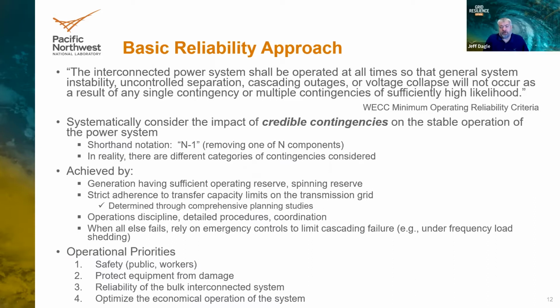There are important measures like spinning reserve, having more generation online than needed at any given time, and emergency controls. If frequency is high, that means we have more generation than load; if frequency is low, we don't have enough generation. If we need to trip generators to protect them from damage, that would be bad if we already have a low frequency condition. So utilities install under frequency load shedding as an emergency control to bring things back to stable operation. All of this is done with prioritization.